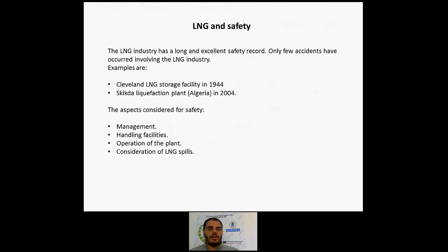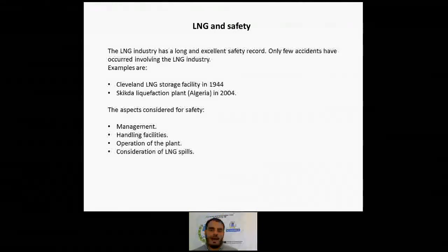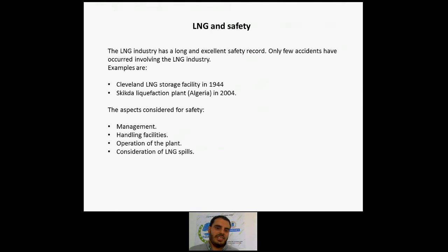The estimated thermal hazard distances, even from a pool fire associated with the largest capacity LNG carriers in operation, involve significant impact to public safety and property contained within approximately 500 meters of a spill, with lower public health and safety impact at distances beyond approximately 1600 meters. However, the studies found that pool fire and vapor dispersion hazard distances are significantly influenced by site-specific environmental, topographical, climatic and operational conditions, including the breach and spill size.